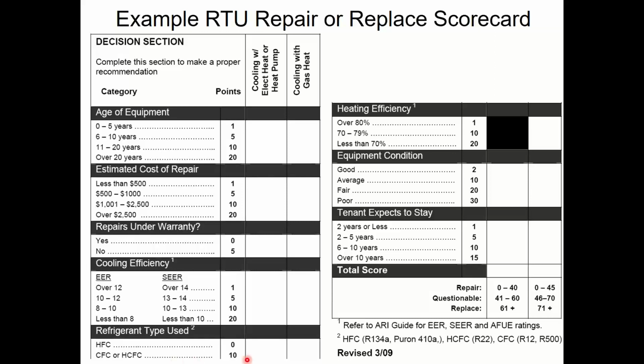What kind of refrigerant do you have? Do you have ones that are obsoleted or ones that are not obsoleted? By the way, we're going to have to update this chart because if you didn't know, package systems for the past 10, 15 years, and for my company since the 90s, we've used R410A. A lot of systems have R22, which is what you guys typically call Freon. Freon R22 is completely obsolete. That's completely off the market. You can't even buy equipment with that anymore.